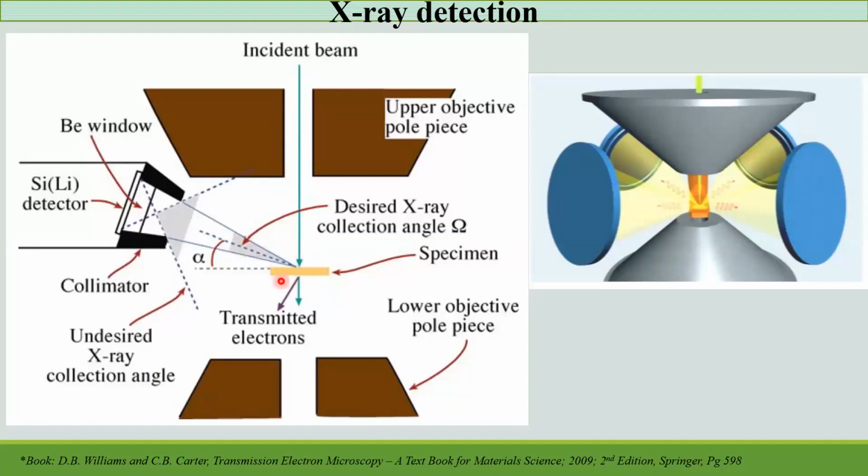So that's why we need to balance here with some tilting angle to get electron and then X-ray. But in advanced TEM, at least the STEM I was using, which has a Super-X detector, which means there are detectors at 4 different angles. So you don't need to tilt the sample. It gets X-rays from all the angles, and these advancements are more specific for chemical quantification.